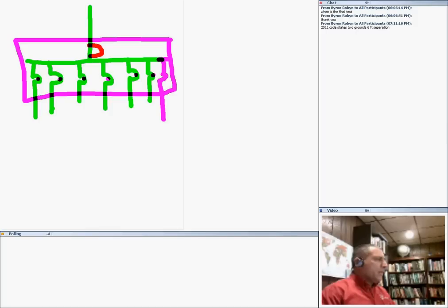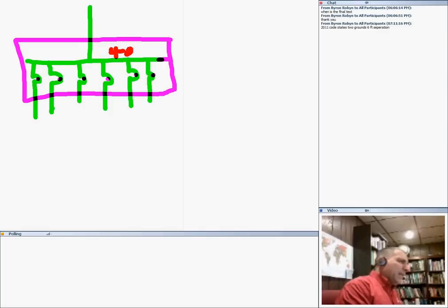So again, about the 6 disconnects, you can have 6 disconnects without a main. Who cares about this? You can, and then my friend, you have cheaper equipment if you maintain a 6 disconnect rule. So with 6 disconnects, I need a panel with no main. So if this was a 400 amp, you saved yourself a 400 amp circuit breaker here, which is an arm and a leg. It costs you good money. You were directed to the switch gear.